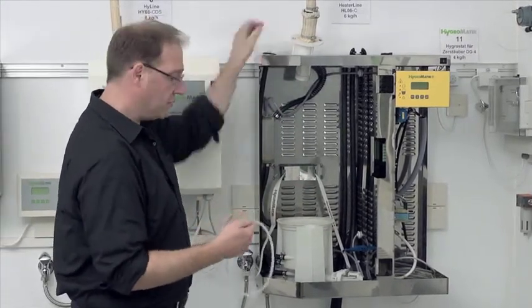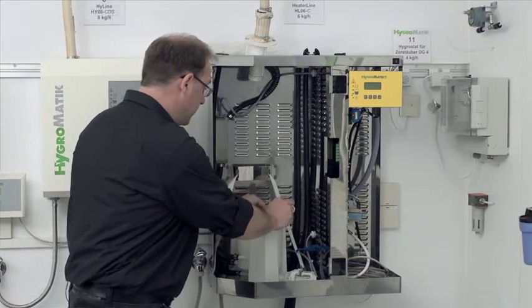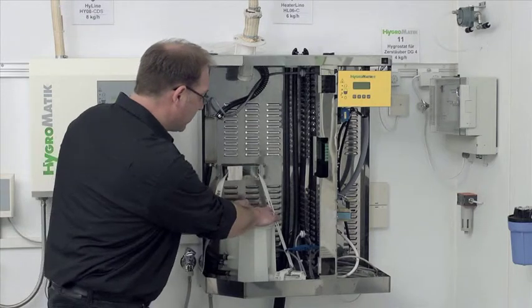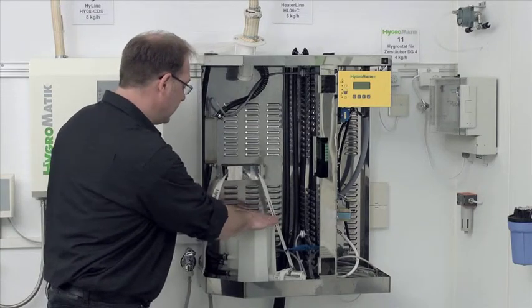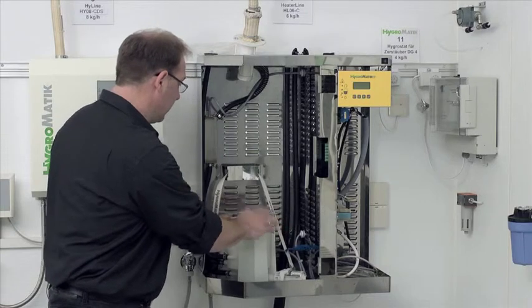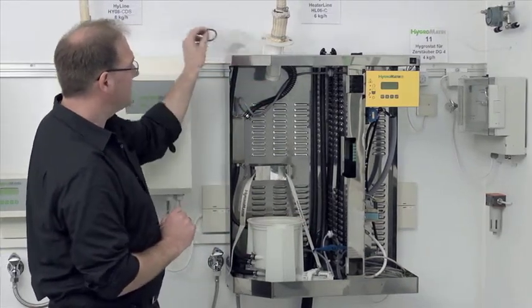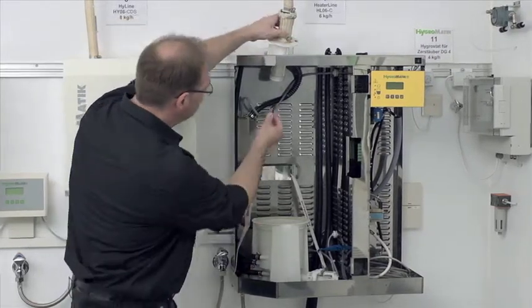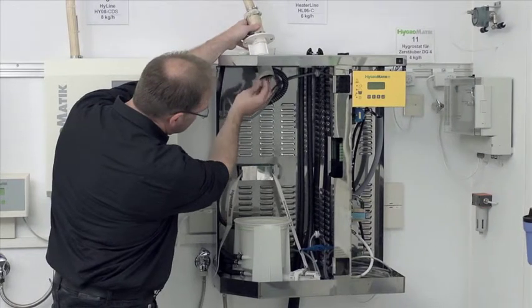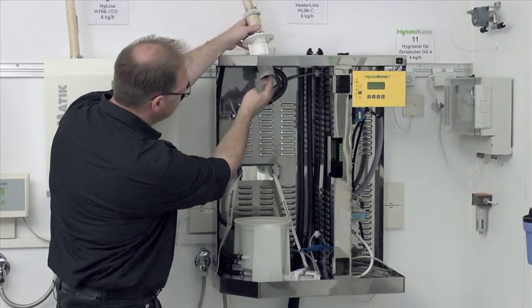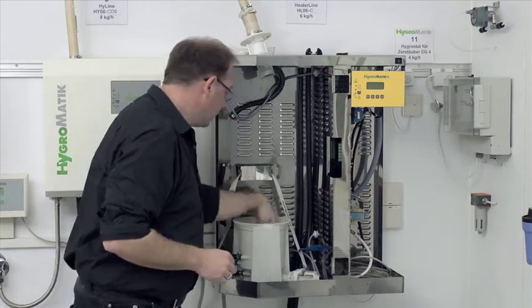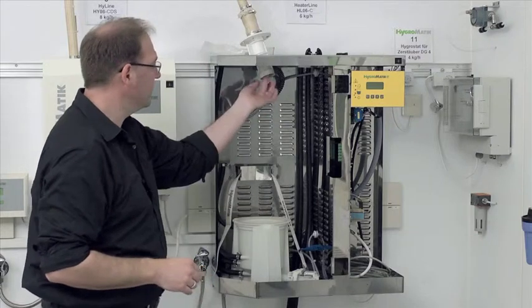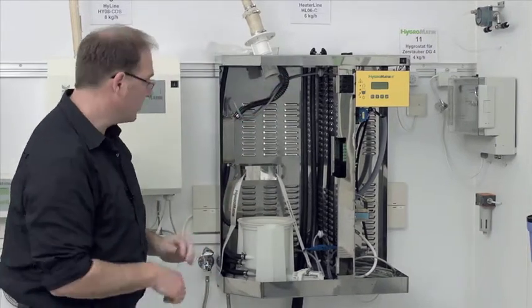I have for one the large O-ring, the silicon O-ring here for the base. You will notice that it is a bit oversized, but that is important in order for it to seal tight. And up here in the steam hose adapter we have another O-ring which we will insert. Up here there is a little groove. Now the O-ring is seated right. I am making it a bit wet, the O-ring. There is always a little water in here. I can use it. So all that will come together better in a moment.